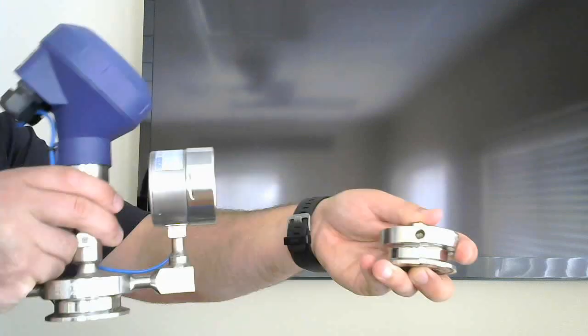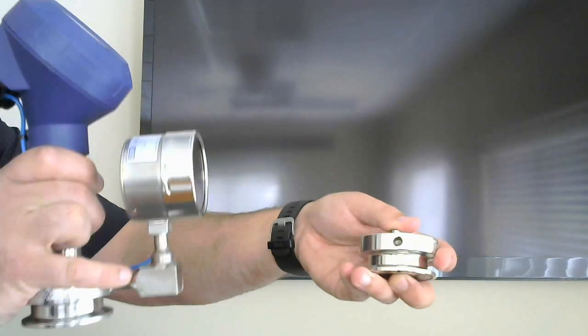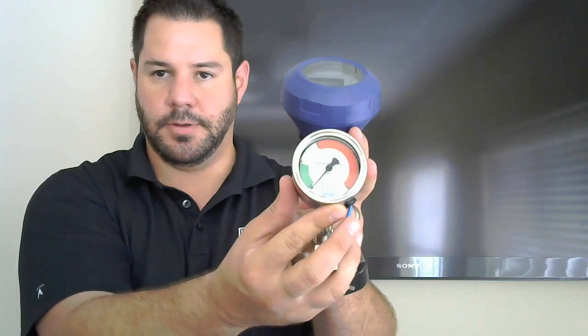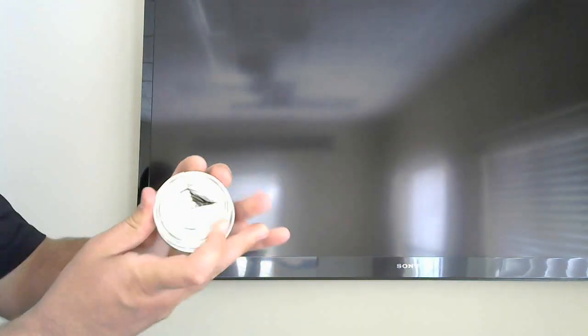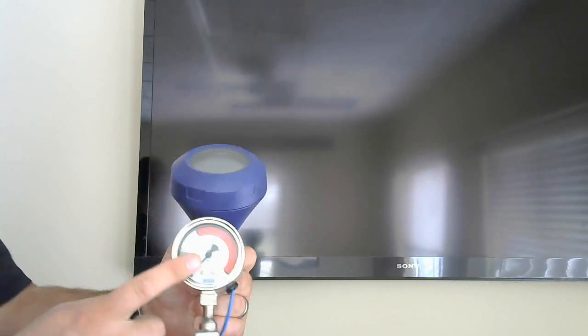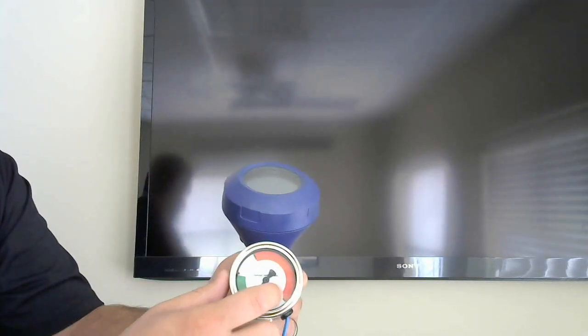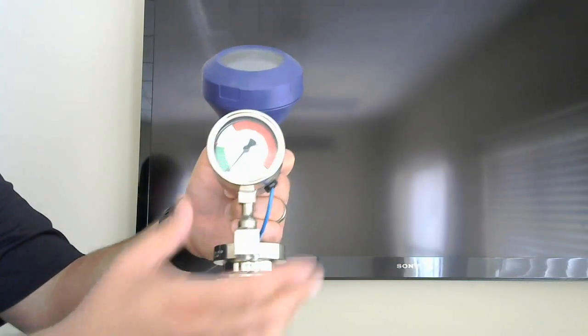So you've pulled your vacuum out, and your vacuum is what's reading on this monitor right here. As your vacuum's reading on this monitor, when and if you lose that vacuum, meaning your diaphragm has failed, if one of these diaphragms fails, which typically is always going to be your process side diaphragm, the lower one, then you're going to lose that vacuum, and it's immediately going to take this gauge from green to red, indicating that you have lost your vacuum in this.